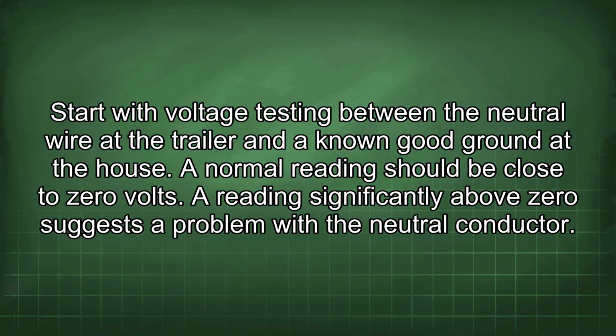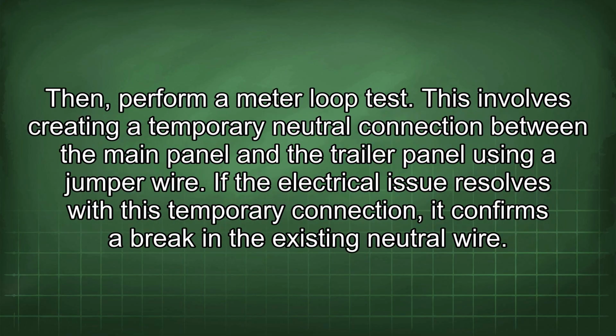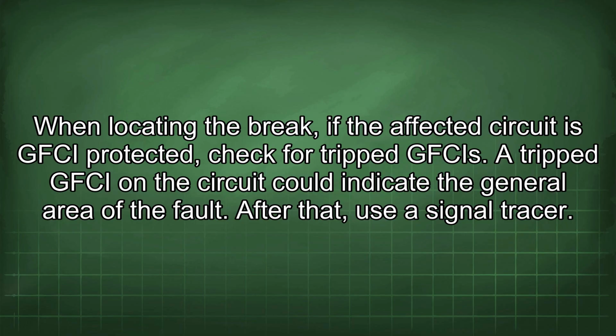Start with voltage testing between the neutral wire at the trailer and a known good ground at the house. A normal reading should be close to 0 volts. A reading significantly above 0 suggests a problem with the neutral conductor. Then perform a meter loop test. This involves creating a temporary neutral connection between the main panel and the trailer panel using a jumper wire. If the electrical issue resolves with this temporary connection, it confirms a break in the existing neutral wire. When locating the break, if the affected circuit is GFCI protected, check for tripped GFCIs. A tripped GFCI on the circuit could indicate the general area of a fault.